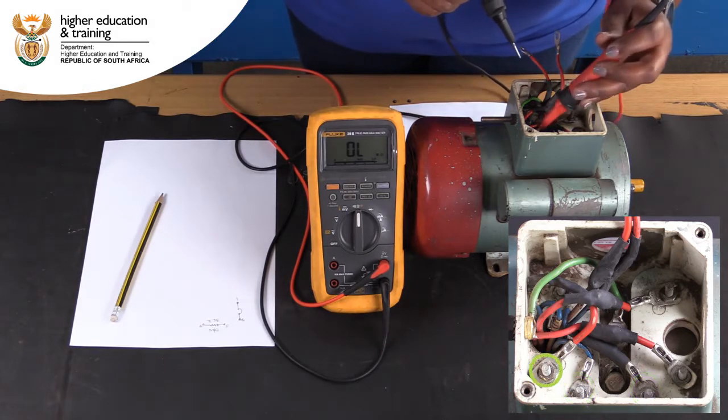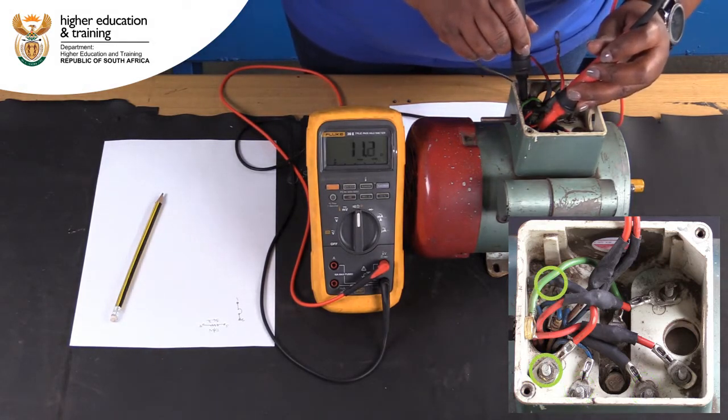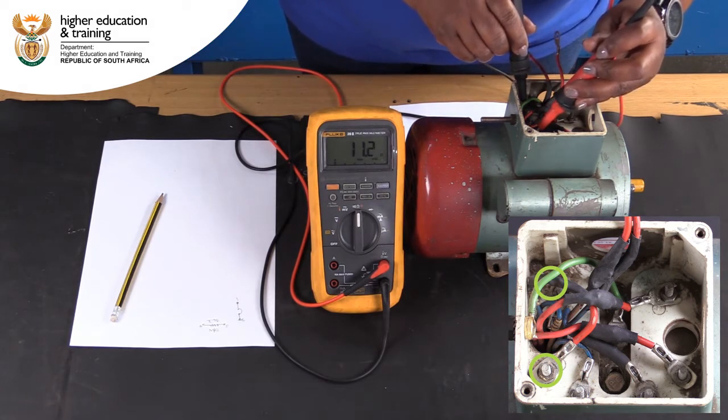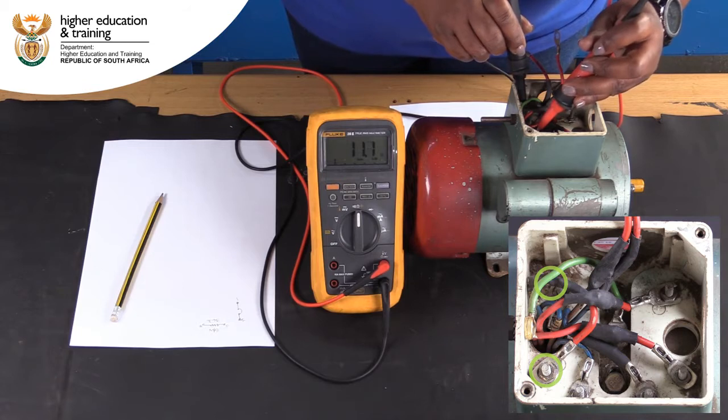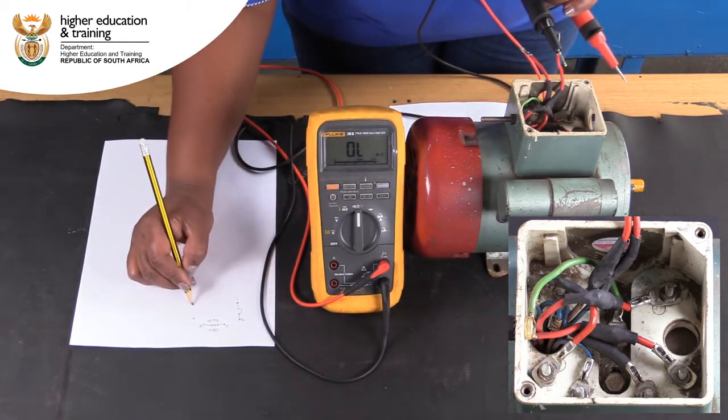Between posts 5 and 6, we get a lower reading of 11.1 ohms. Remember that the run winding will always have a lower resistance than the start winding. Therefore, this indicates the run winding.